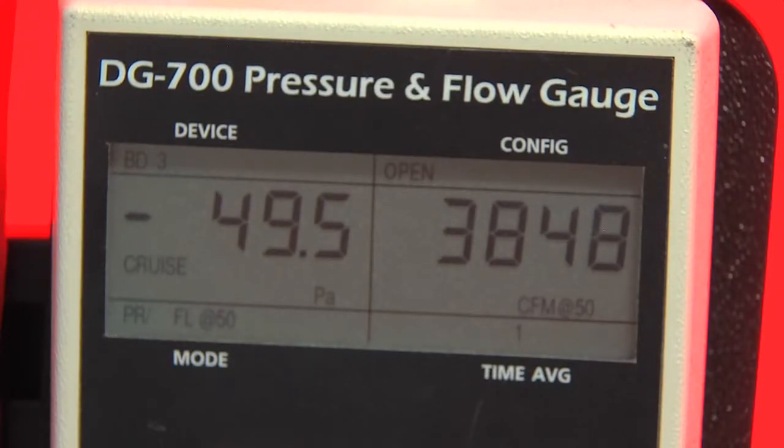So with our threshold sealed here, we went back out and looked at the reading, and it's dropped to about 3,850 cubic feet per minute. So this one area was accounting for 100 cubic feet of air exchanging per minute — it calculates to probably about 3% of the leakage that we're measuring.